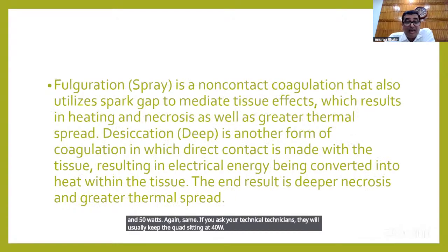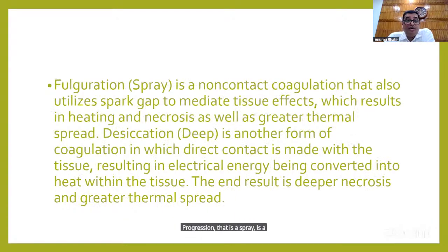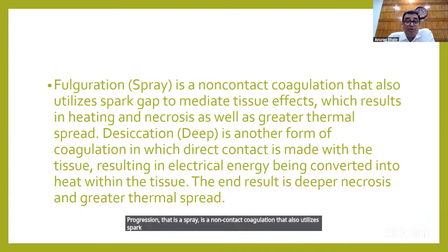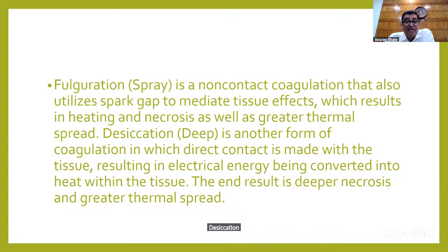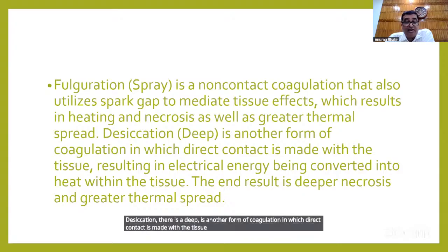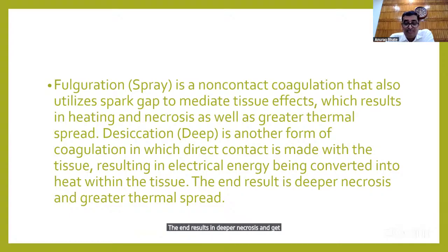Fulguration, that is a spray, is a non-contact coagulation that also utilizes spark gap to mediate tissue effects, which results in heating and necrosis as well as greater thermal spread. Desiccation, that is a deep, is another form of coagulation in which direct contact is made with the tissue, resulting in electrical energy being converted into heat within the tissue. The end results in deeper necrosis and greater thermal spread.